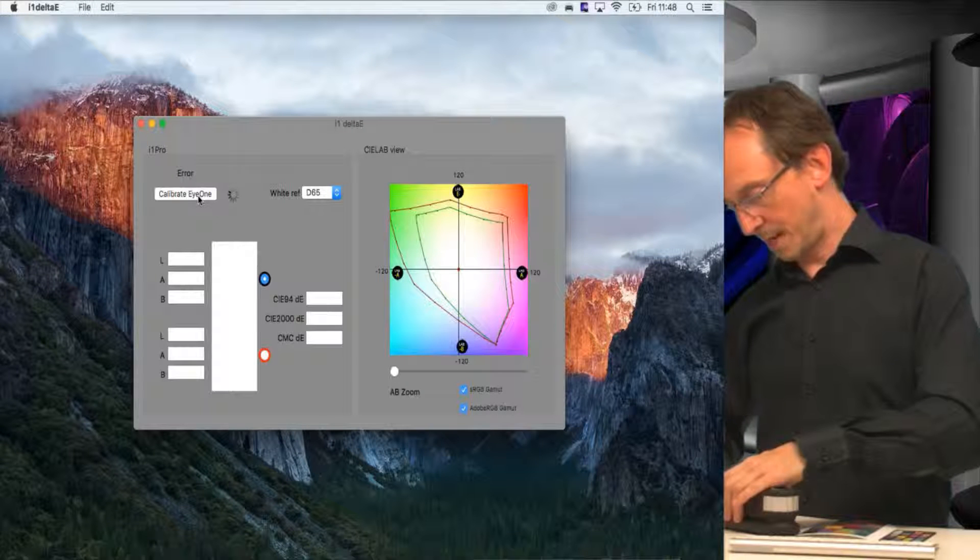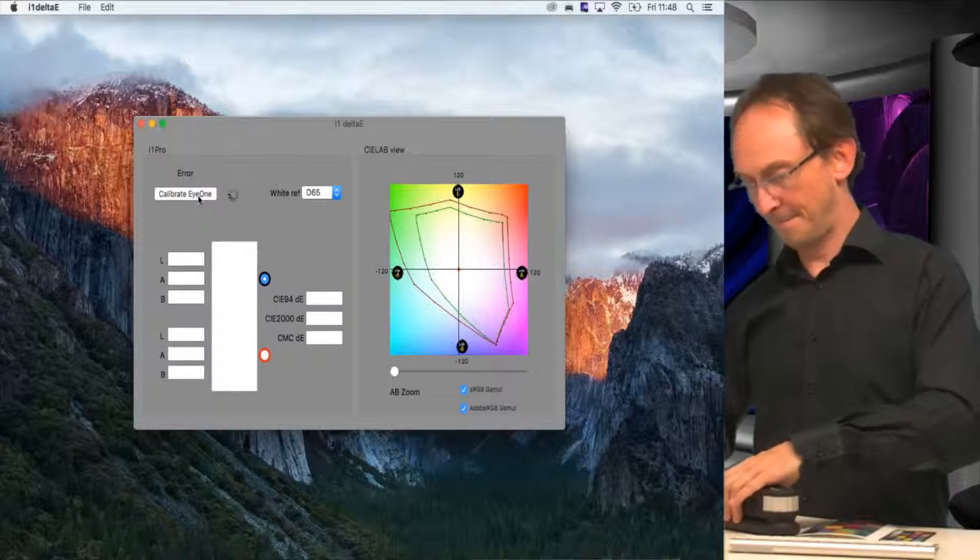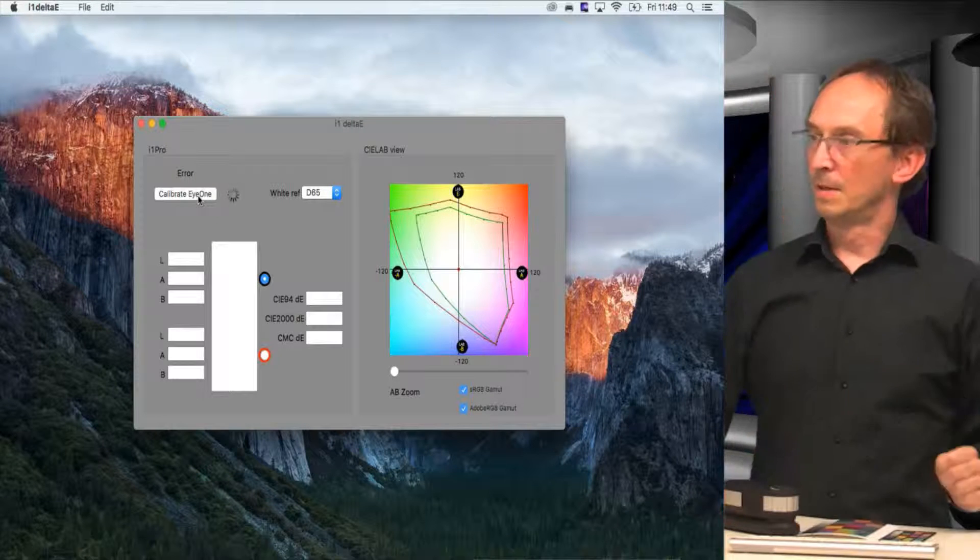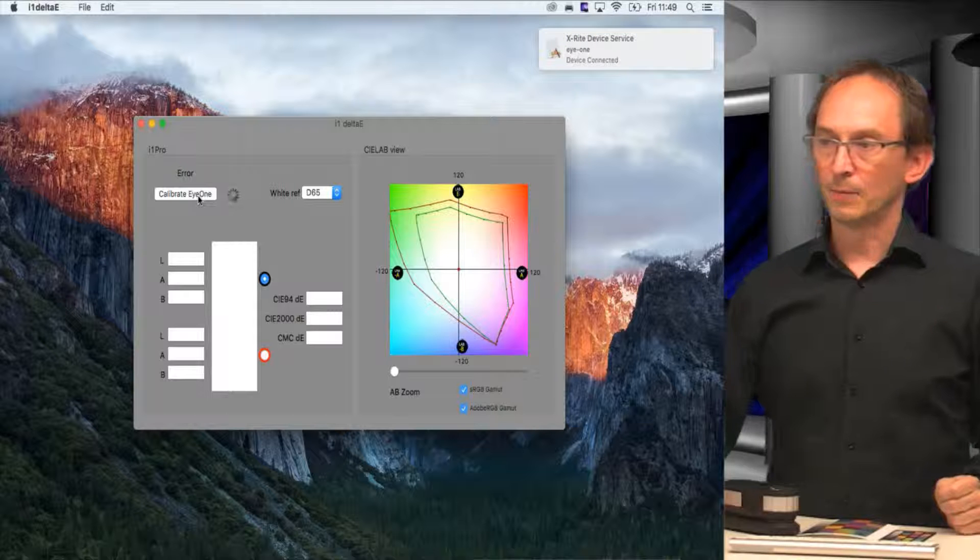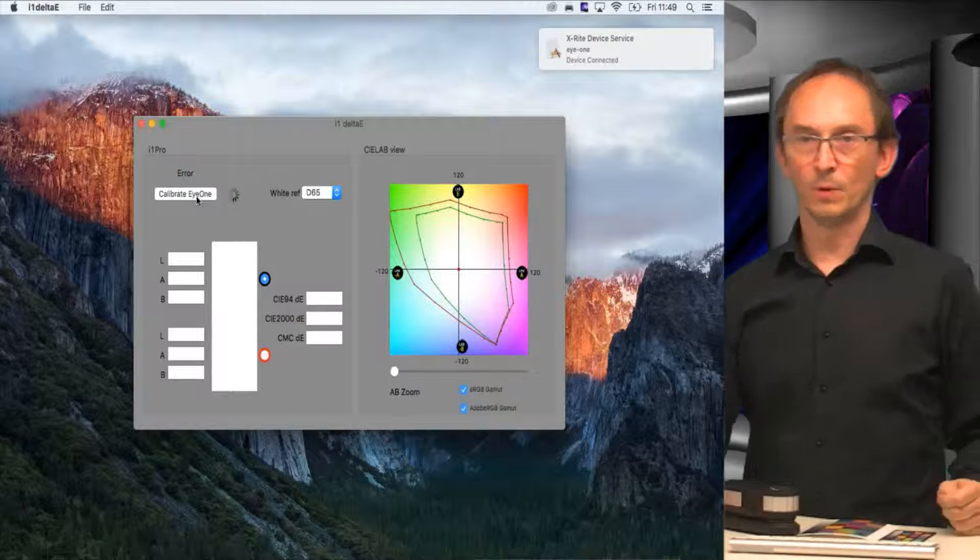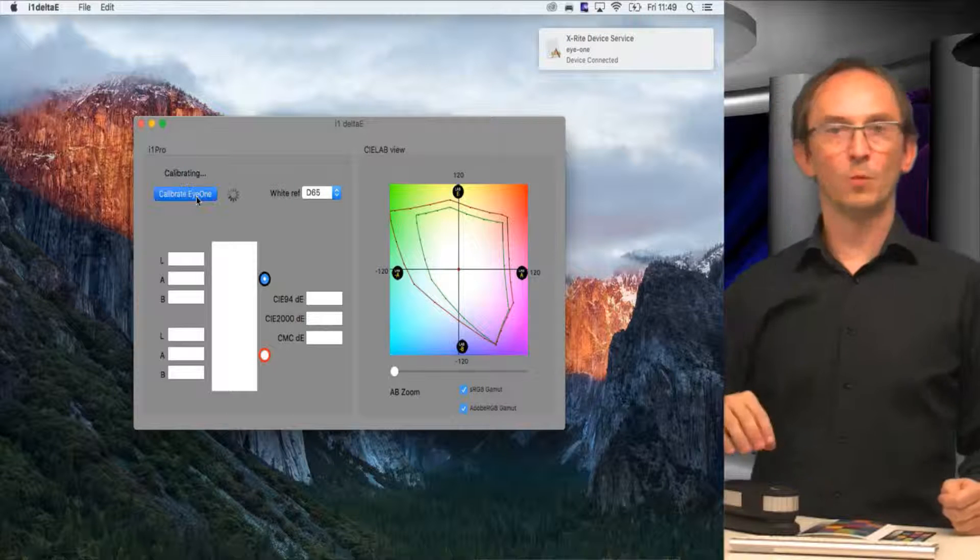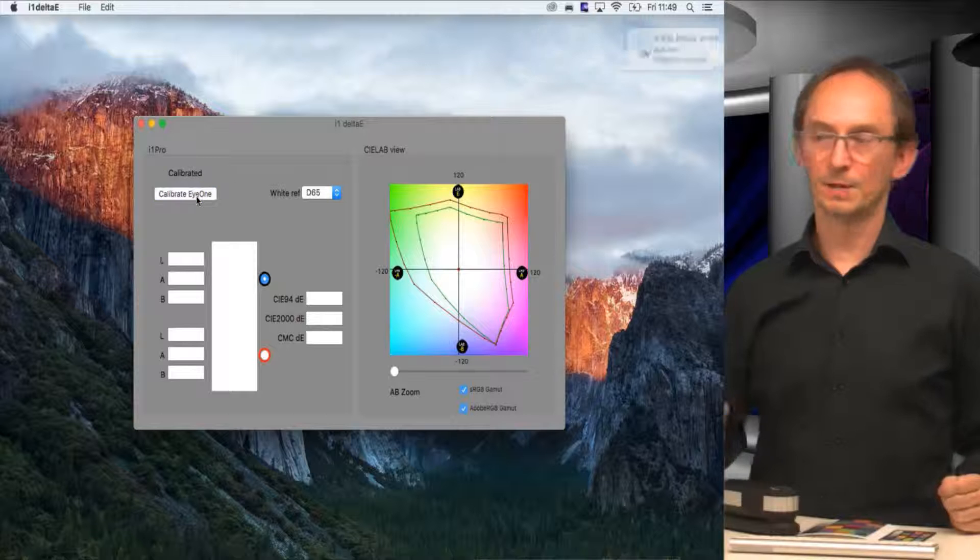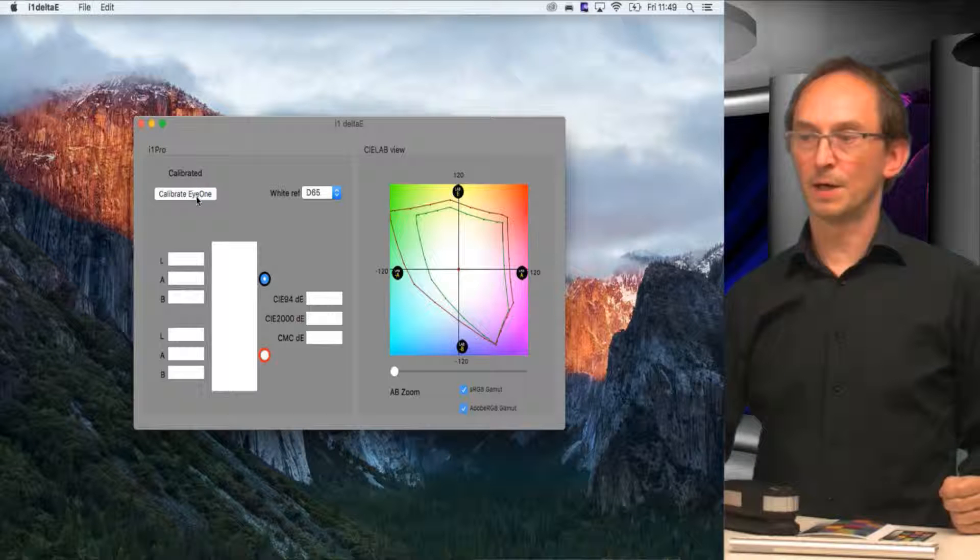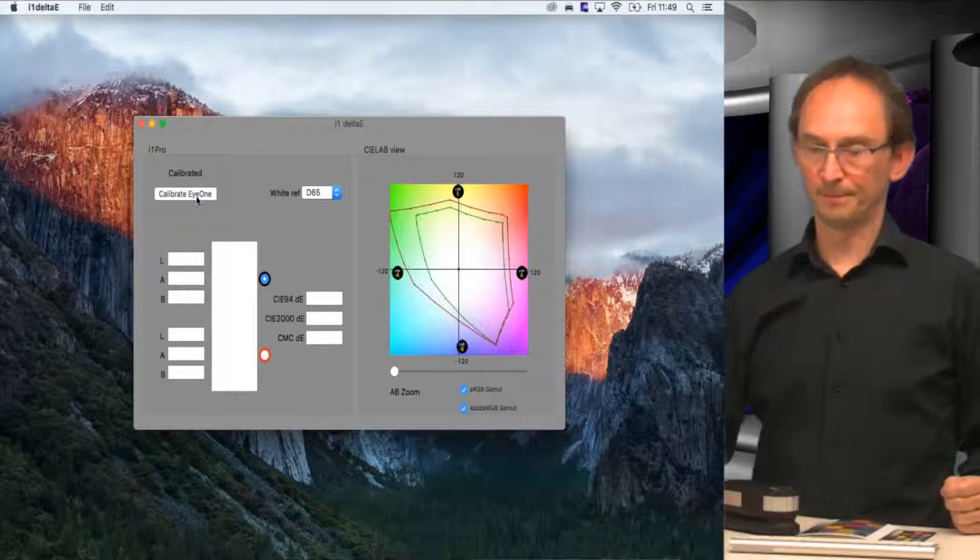So let me plug it back in. If I then hit calibrate, it will actually measure the white reference point and calibrate itself. So now it says it's calibrated.